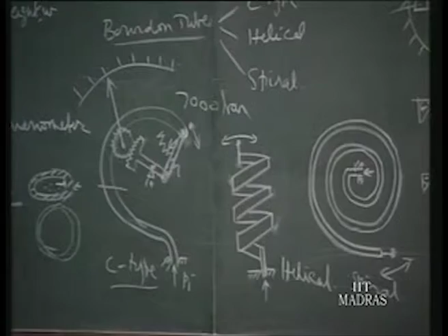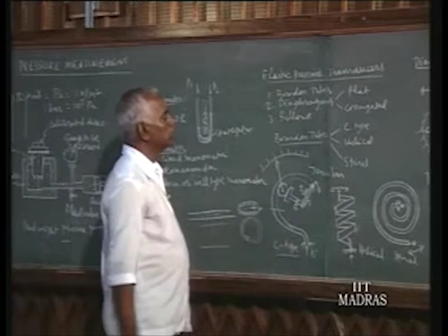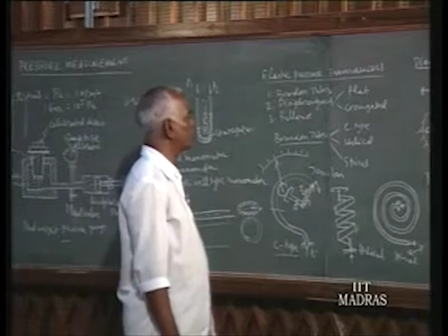But for dynamic pressures, we should be careful with the tube carrying the pressure, because when a pressure fluid flows through any small piping, that frequency is damped out. Whenever we carry dynamic pressures to an instrument, we should have a sufficiently large cross section so that the pressure variation is truthfully transmitted to the instrument end. Otherwise, the dynamic pressure taking place in this vessel cannot be carried by a thin tubing to an instrument, or we have to mount the instrument on the tank or pressure vessel itself wherever we want to measure. Those precautions we have to take.